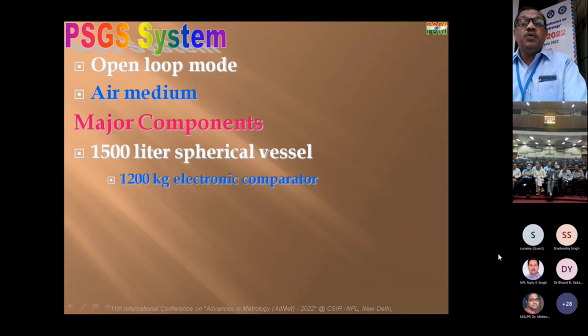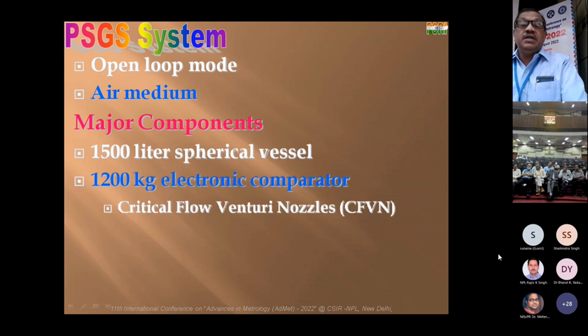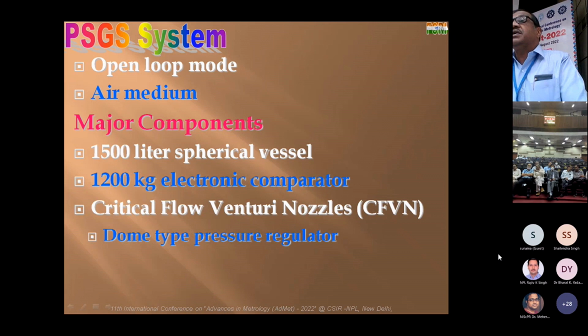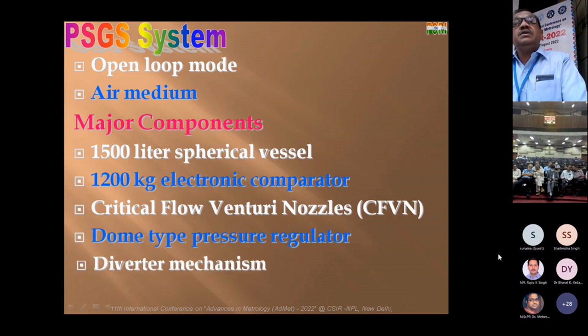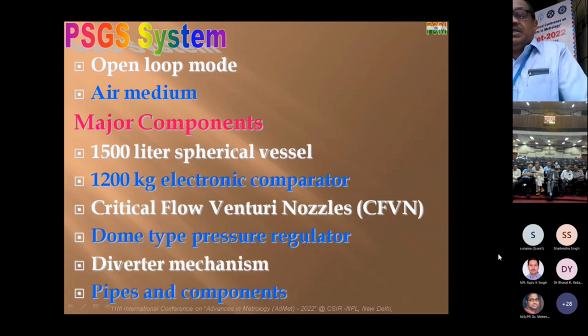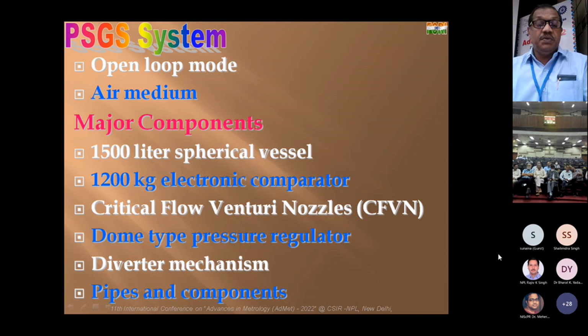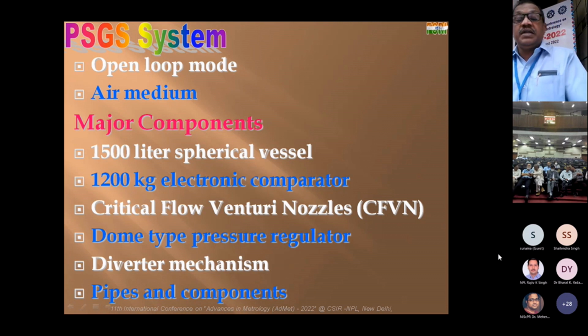Basically, it is working in an open loop mode. That is, we take compressed air from a reservoir, process it, and then finally discharge it. So it is in an open loop mode, and we use compressed air with pressure up to 20 bar. The major components of the gravimetric system: we have a 1500 liter spherical vessel in which we collect the air, and we measure the air collected in the spherical vessel.